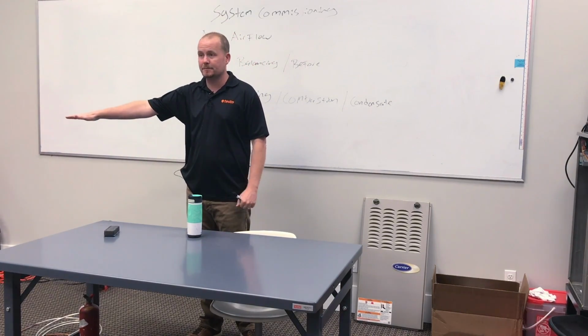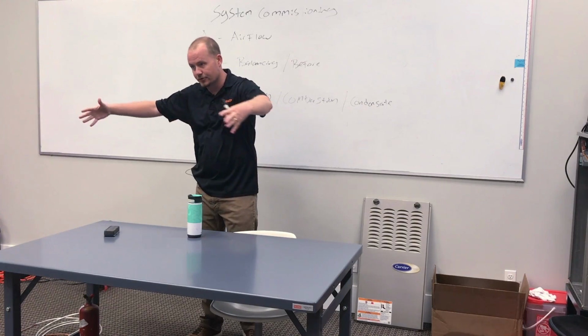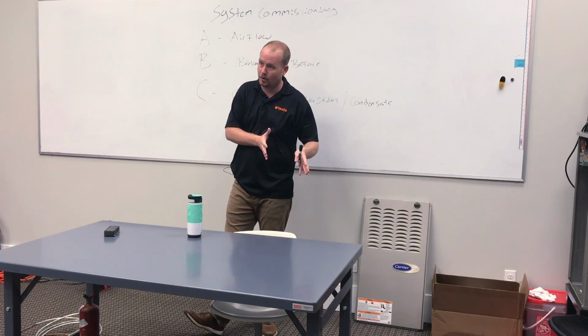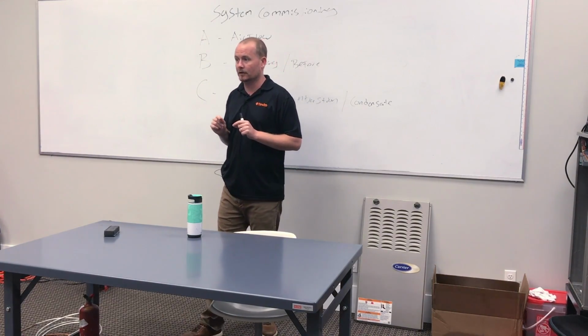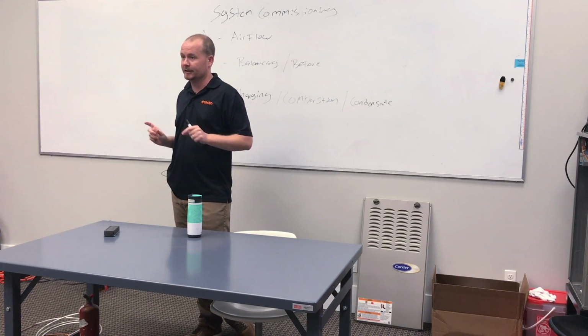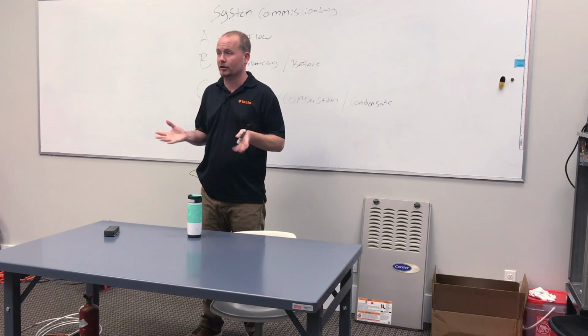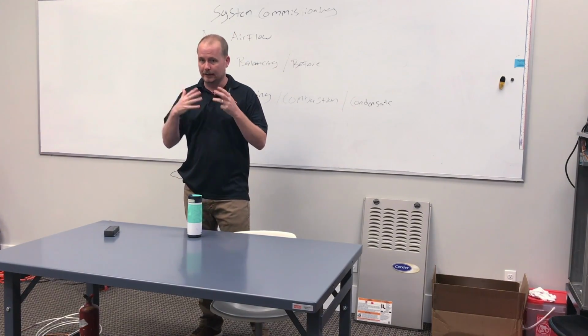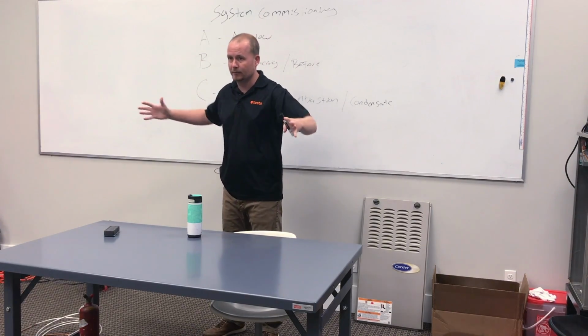Confirm your airflow. Make sure your airflows are right. Condenser fan's putting air out the top. Bushes are trimmed back away from it. It's not too close to the wall. I've seen a couple recently that look a little too close to the wall, so pay attention to that. It's in the installation instructions. We've talked about that. So think about that when you're installing units, but just give your proper clearances.